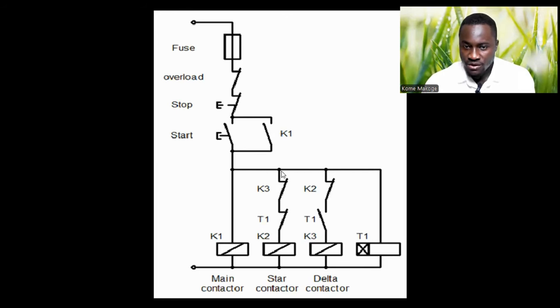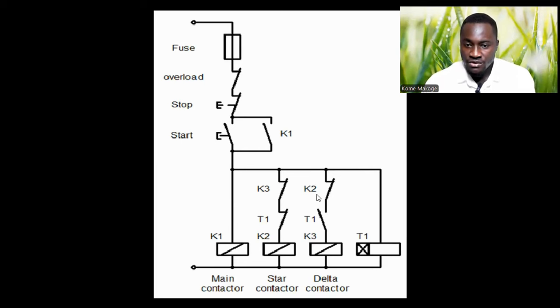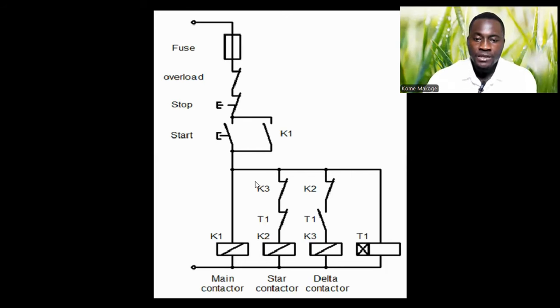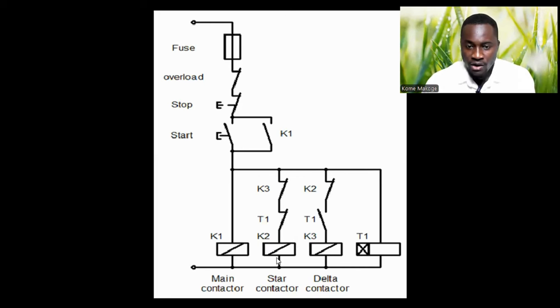Current also moves in this direction, gets to this point, and then moves to the timer, so the timer coil will energize. At the same time, current gets to this point but is not able to move down because this contact is a normally open contact. It gets to the closed contact K3, moves down, gets to the normally closed contact of timer T1, still moves down and gets to the level of coil K2 — the star contactor. So at this point the star contactor coil is energized, enabling the motor to operate in star.